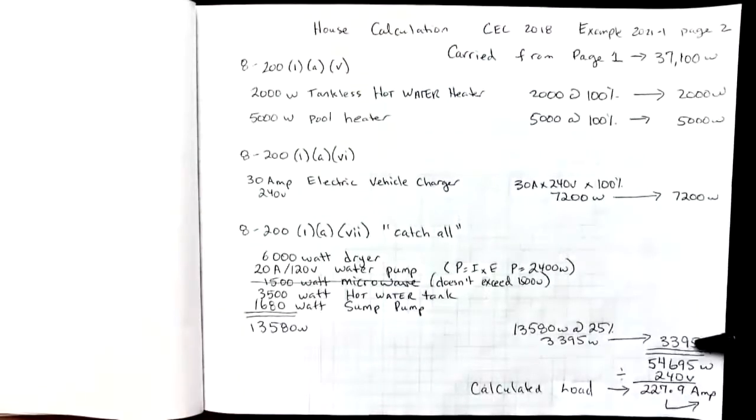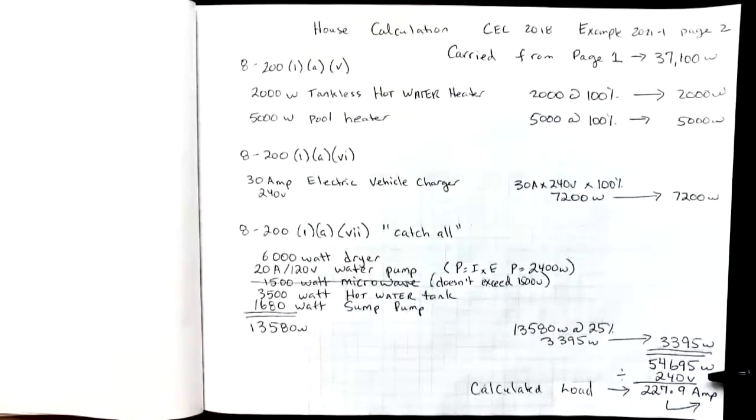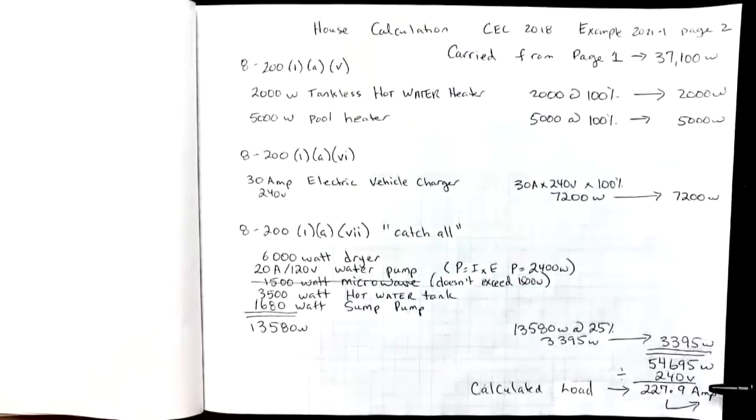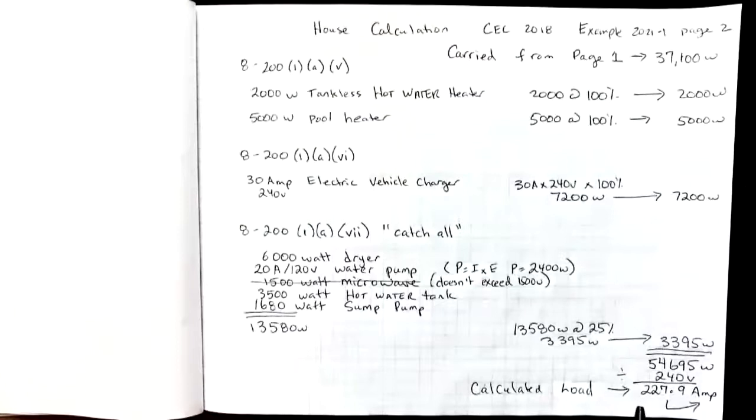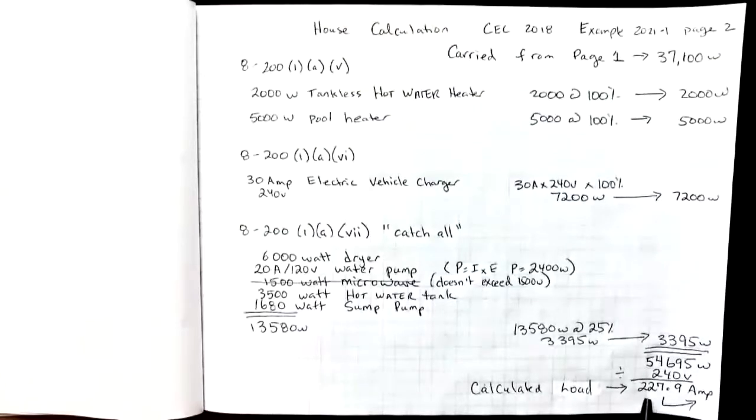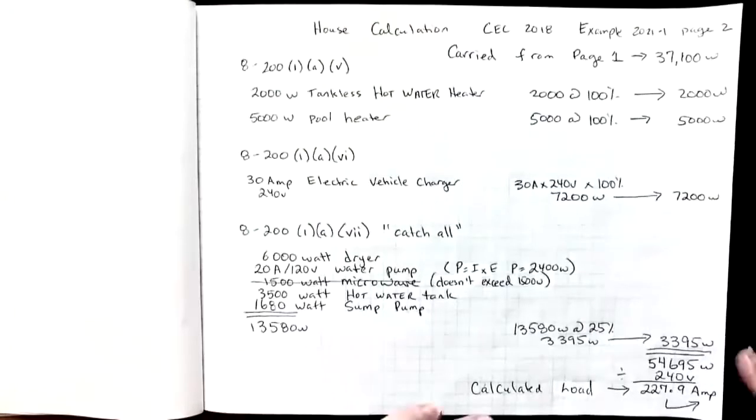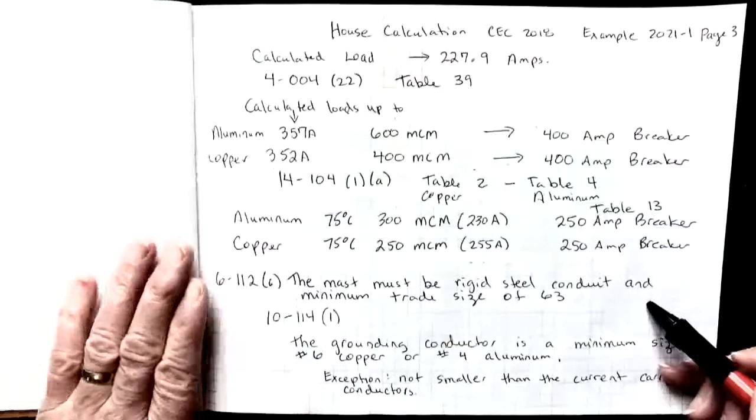I add all of these up, including the previous page which was carried forward here, gives me 54,695 watts. The typical home in Canada is fed with 240 volts, so I divide that wattage by 240 volts. And my calculated load then is 227.9 amps. I'm going to carry that forward to the next page so we can look for the wire and the breaker.